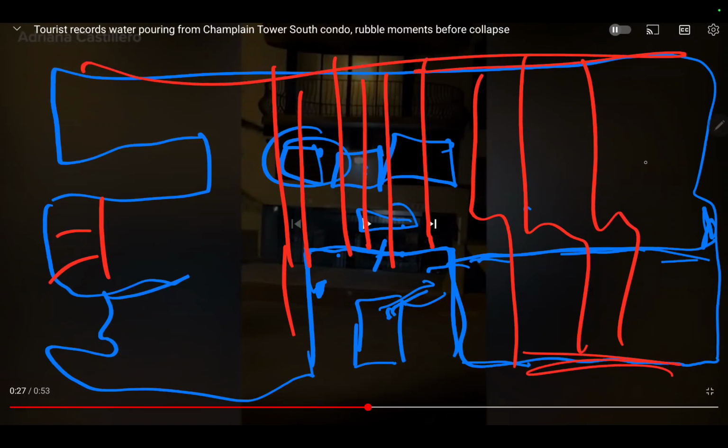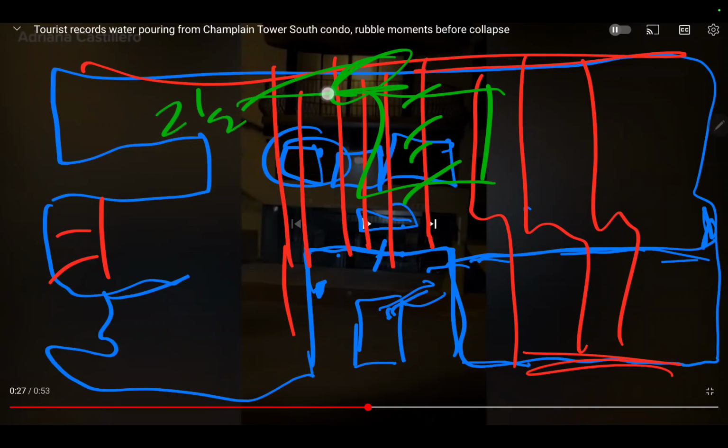We get this structure collapsing here. They take out these pipes, like I said. Taking out this last pipe in the back wall, the 2.5 inch pipe. Perhaps that's why that wall settled up there. That part of the floor settled up there. It could be sitting on top of the pipes. I don't know that, and this didn't disclose that with us, but that wall's anchored to the pipe. That pipe's anchored to the wall back there. But I believe it's fractured, and that's where you're getting your low pressure, and that would be your indicator.